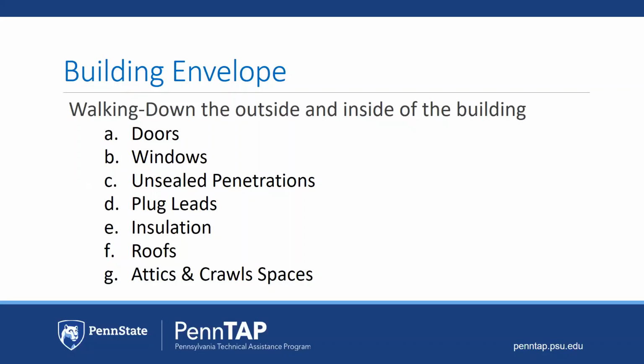For insulation, we recommend using an infrared camera to walk the perimeter, interior and exterior, to inspect for damaged locations and penetrations and missing insulation. Also consider your doors and windows with this infrared camera. For roofs, white and clean are the most energy saving. Dirt can change the color and thus you'll lose out on your improvement. Also look for standing water. Standing water will increase the possibility for mold and leaks.